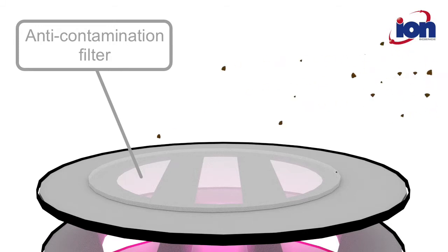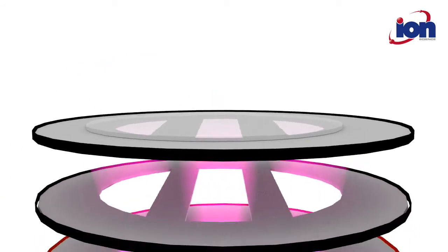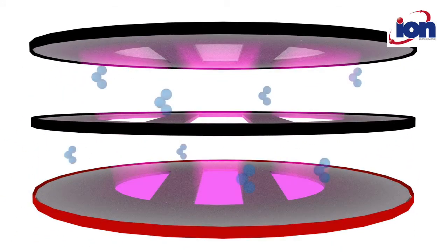The Mini PID also has an anti-contamination filter. This blocks airborne particles from entering the detection chamber and helps retain tiny amounts of ozone generated in the chamber. Ozone actively cleans the electrode stack, ensuring optimum performance is maintained.